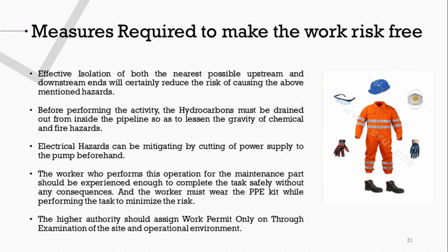What are the measures required for risk-free work? There must be effective isolation of the working site from the active system. The portion in which the maintenance work is to be done should be isolated from the whole system, which will greatly reduce the hazard associated with the activity. Draining the hydrocarbon from the pipeline is also an essential step because it will reduce the intensity of chemical and fire hazards.